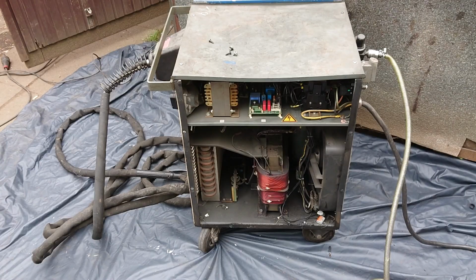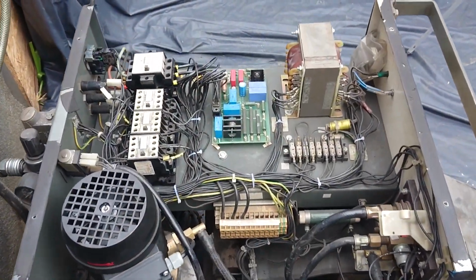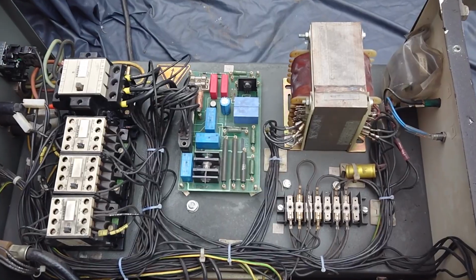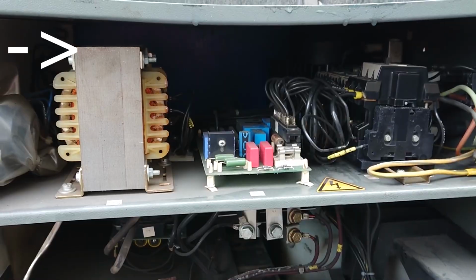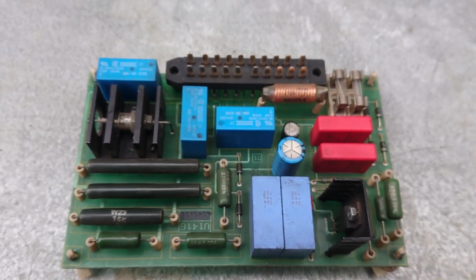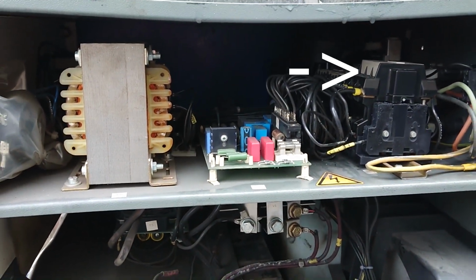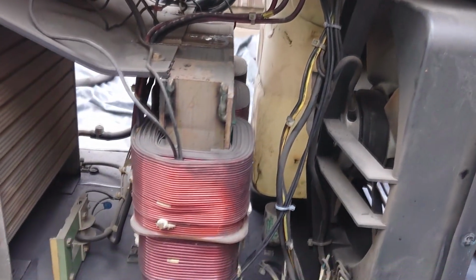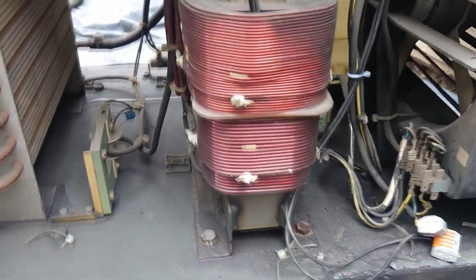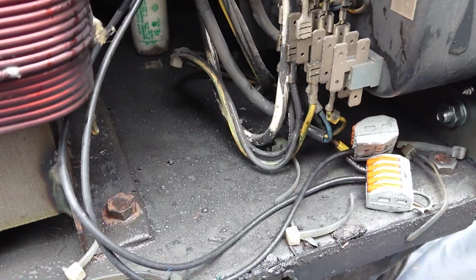Let's get right into it then: inspect this piece of equipment, identify the components, assess the damage, and find the fault that causes the fuse to blow. Up here we have a small single-phase transformer and a board that carries the driver for the high-voltage generator. Next to it, a number of three-phase contactors. Below it, a high-voltage transformer, three-phase rectifier bridge, and a capacitor. Finally, in the bottom, from right to left, a fan with motor capacitor, a three-phase transformer, a current relay, and a heat exchanger. I also found these modern Wago clamps down here, and I can assure you we did not have those back in '87.